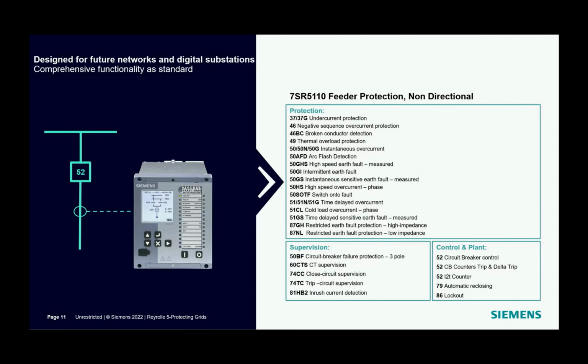This provides flexible, independent automatically closing sequences for the three-phase unearthed faults, restoring power flow after transient network faults. When a 7SR5 is used as a backup protection for transformer protection solution, let's say, restricted earth fault protection is also available.